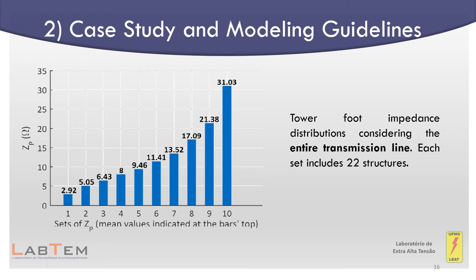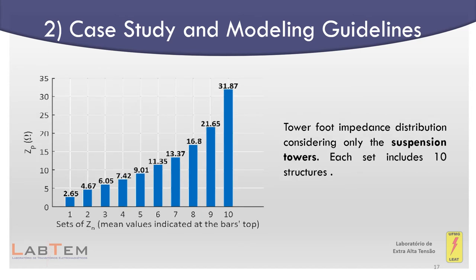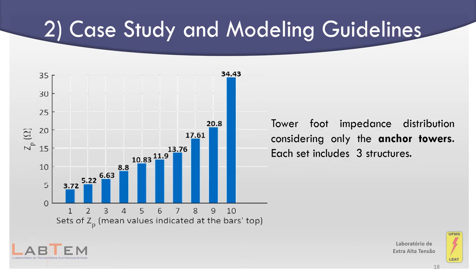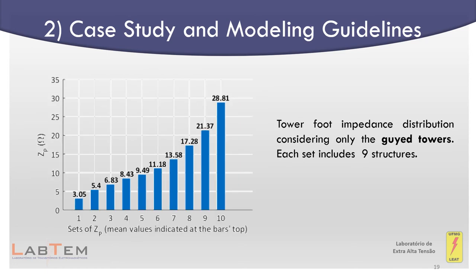The same procedure, but specifically considering the suspension, anchor, and guyed towers, was carried out and is presented in the following slides. Here it is represented the tower foot impedance distribution considering only the suspension towers, where each set includes 10 structures. In the next slide it is represented the tower foot impedance distribution considering only the anchor towers, where each set includes three structures. These distributions are used in the methodology proposed by this work.